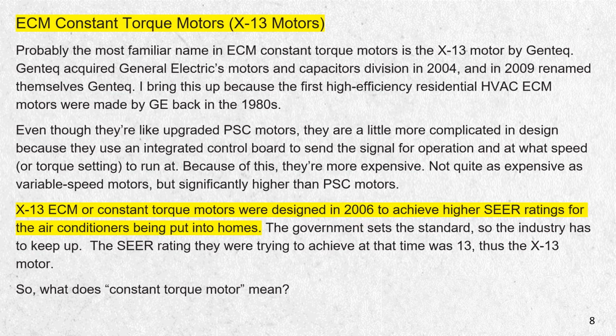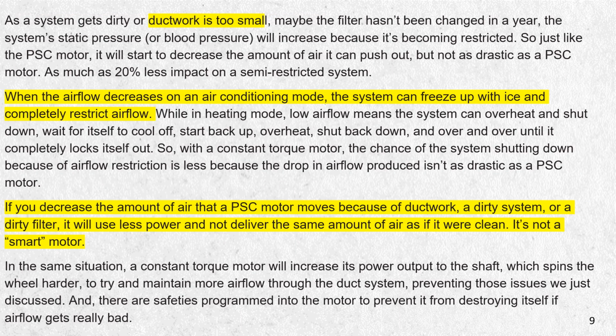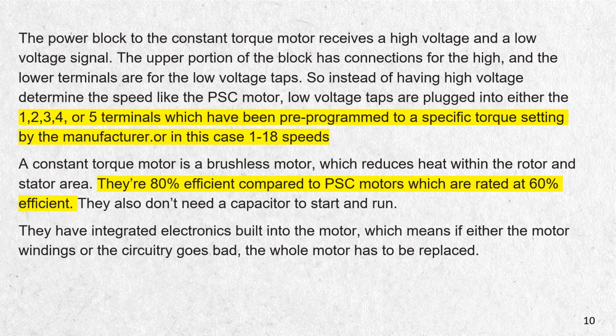Now, what does a constant torque motor actually mean? A constant torque motor, when it can't breathe, or if the ductwork's too small, or the static pressure is too high, or there's resistance, will keep torquing up to deliver the CFM that it's designed to deliver. The old PSC motors, the high, medium, low, were not a smart motor, so they just ran one CFM or one RPM, and then if it got dirty or it couldn't breathe or was blocked, it would overheat the motor and slow down. So the X13 motor is a good design, but it has already gotten better.